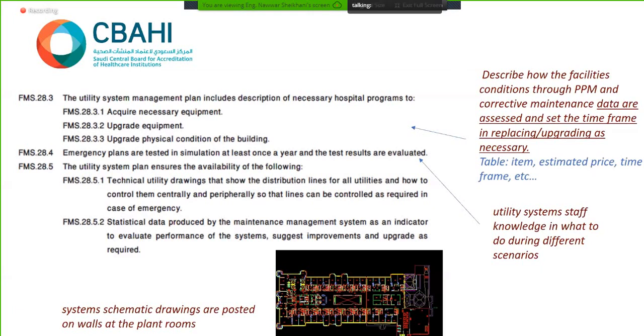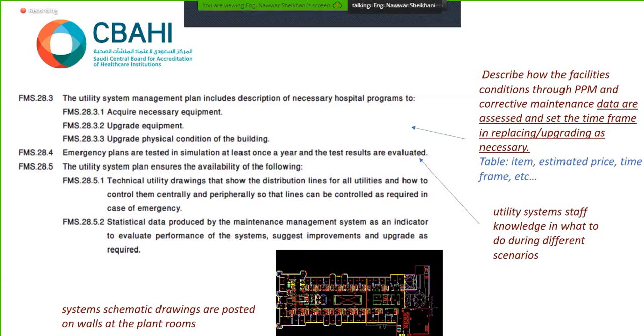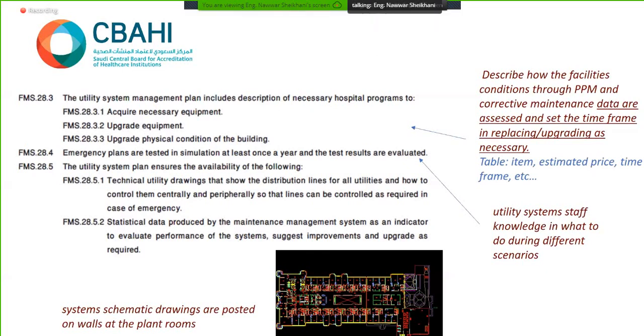28.4 talks about drills, tests, or simulations at least once a year. Remember how Mr. Abdul Mohsen explained conducting fire drills? Here we should have similar drills, but related to the utility system. Assume a scenario where the medical gas network suddenly collapses. What is the scenario, what action is taken? All this should be documented once a year for each utility system.